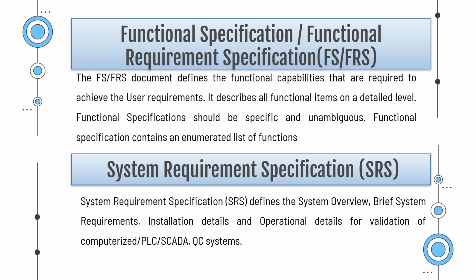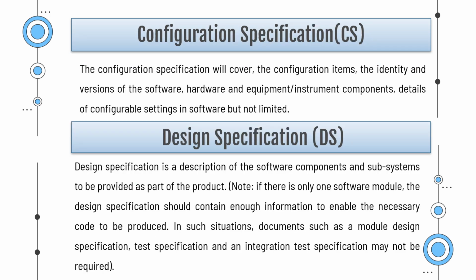System Requirement Specification (SRS). The System Requirement Specification defines the system overview, brief system requirements, installation details and operational details for validation of computerized PLC, SCADA, QC systems. Configuration Specification (CS). The configuration specification will cover the configuration items, the identity and versions of the software, hardware and equipment instrument components, and details of configurable settings in software, but not limited to these.